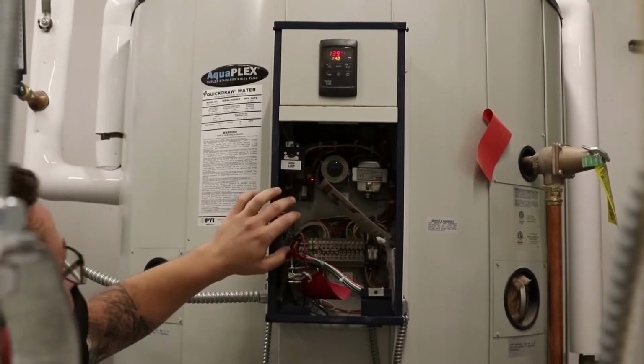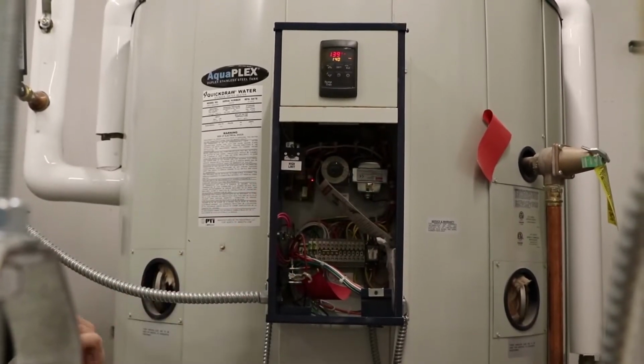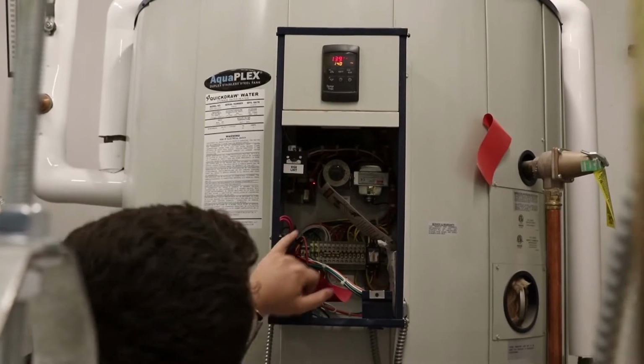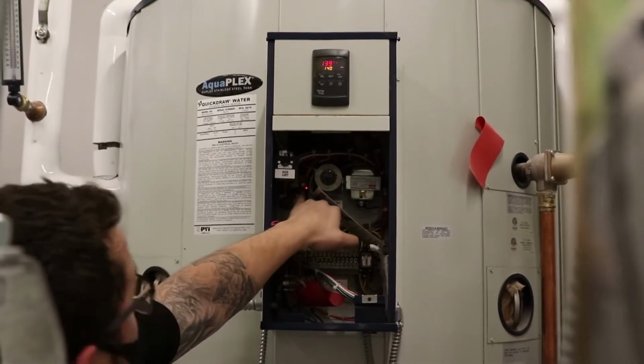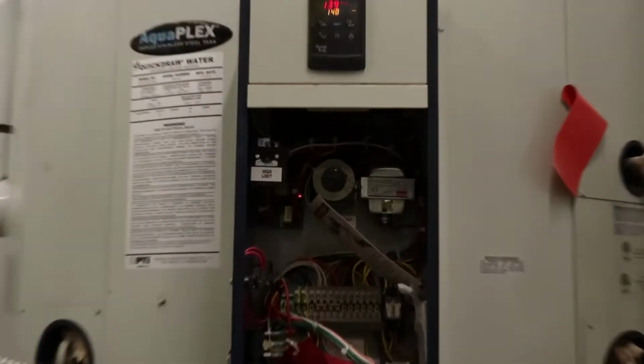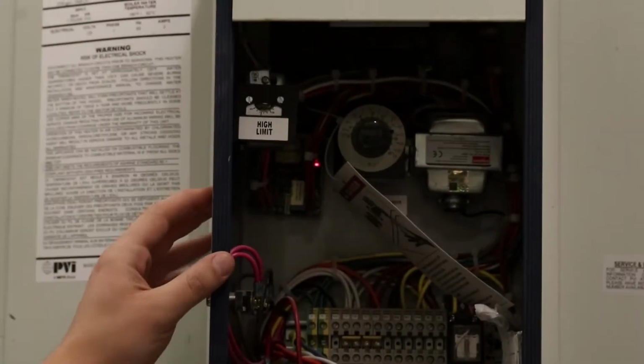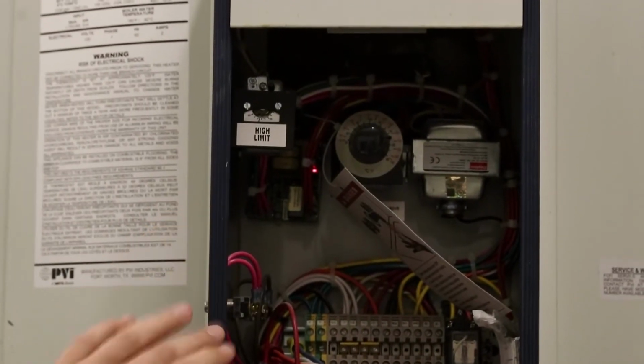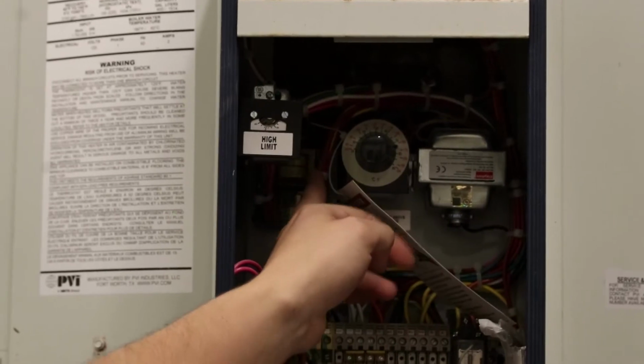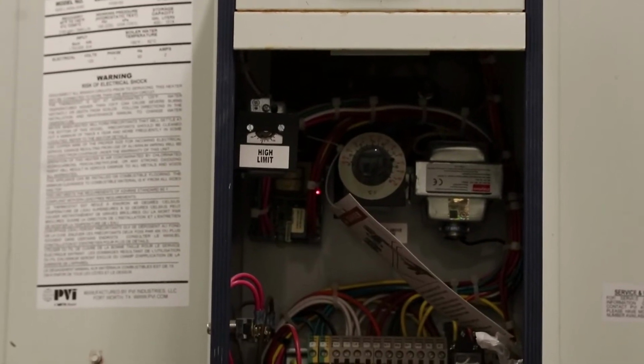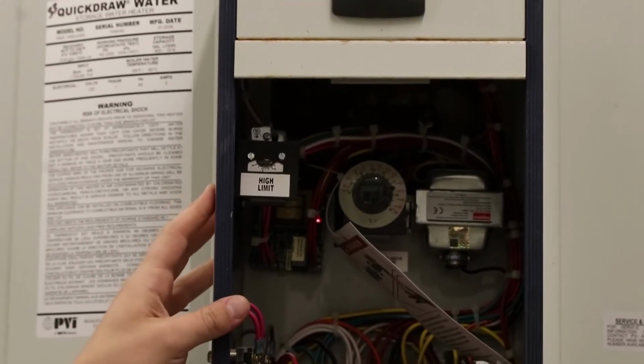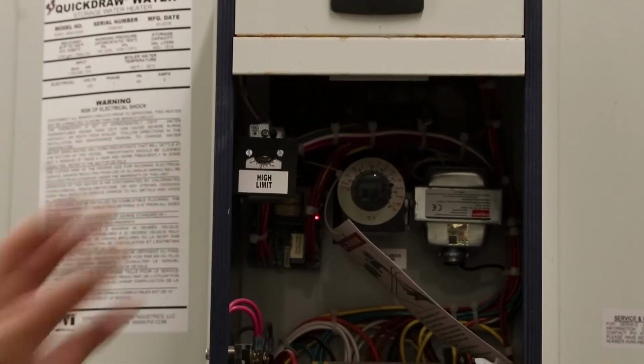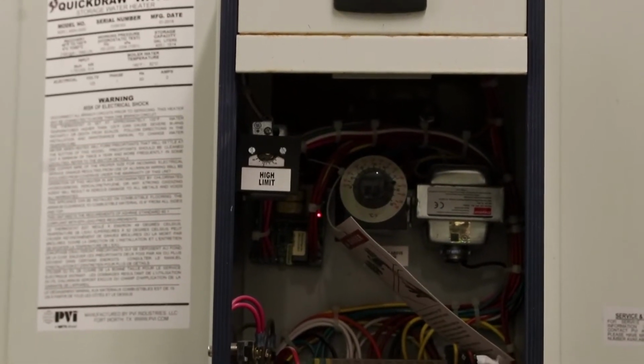The other safety, in addition to the manual reset high limit, is the low water cutoff control. You'll see that green circuit board in the control panel just behind the high limit. And hopefully on the camera you can see there's a red LED light on that board. That red LED light being present tells me that this control is sensing water and is satisfied and is not preventing operation of the water heater.